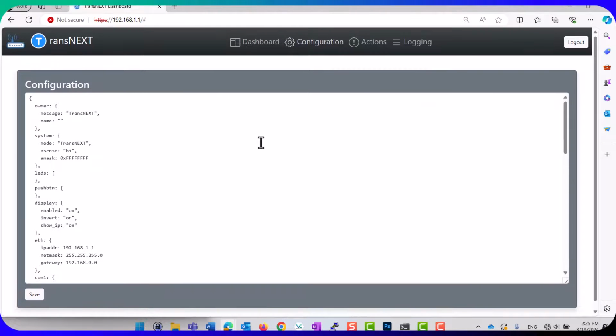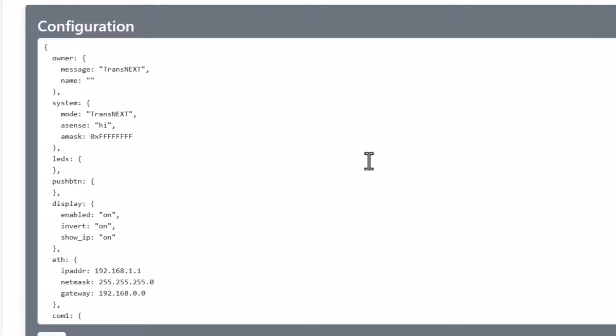So you can see here that to configure this TransNEXT, it's not quite like the Orbit or some of our predecessors, but it is sort of similar to the TransNET in the sense that a telnet connection, and you had to know your codes, so you would enter things like RSSI, mode, X address unit, things like that to program that unit. Those same sort of configs are built in, but they're at least displayed for us to manually modify.